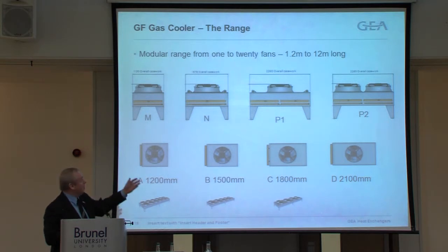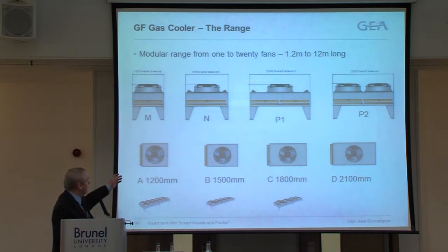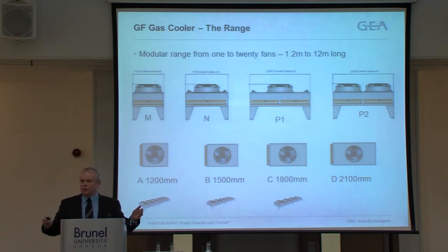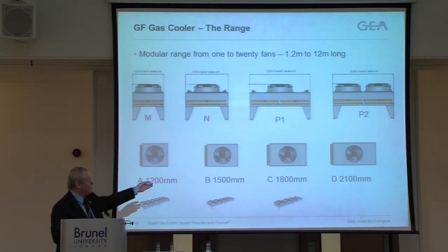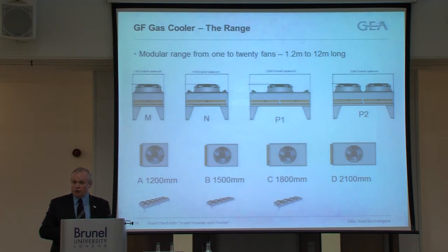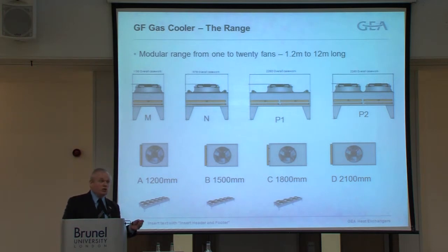2.3 metres wide. We have an intermediate unit that's 1600 millimetres wide, single row of fans. On the double unit, we have single row of fans and then an option for a double row of fans. Each of the fans is mounted under a module. Many years ago, we used to just have one module, 1200 millimetres, one fan, that was it. Today, we now have 1200, 1500, 1800 and 2.1 metres. This enables you to actually select a gas cooler to meet your specific requirements.